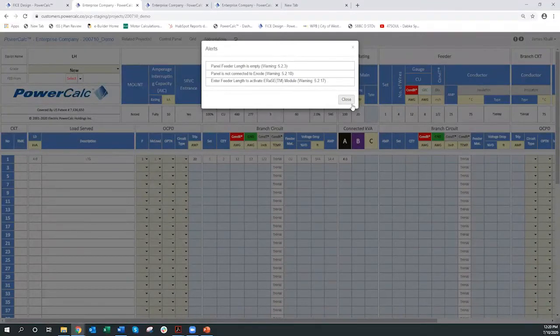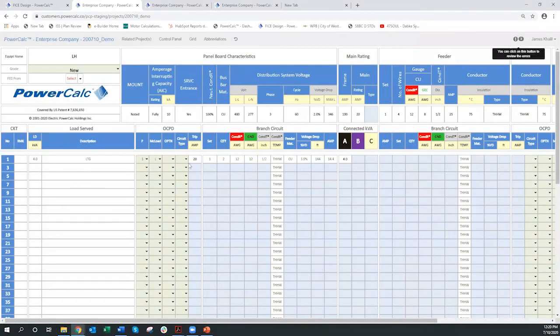Okay, so it gave you the branch circuit. It's a 20 amp, 2 number 12 ground, and a 1/2 inch conduit, and it's a copper circuit. I'm sorry, copper material, and the conductor temperature is THHN. And the voltage drop to maintain 3%, that circuit should not go over 144 feet. And the total amp on that particular circuit is 14.4.